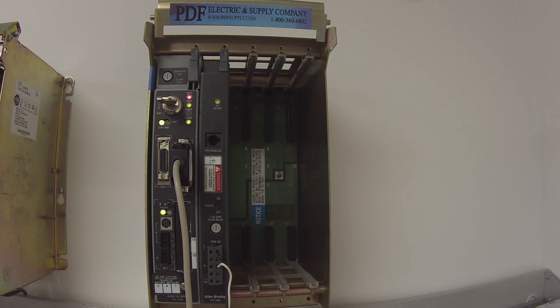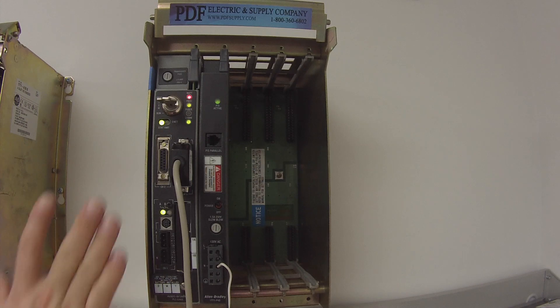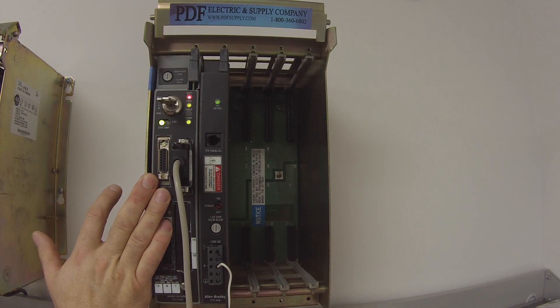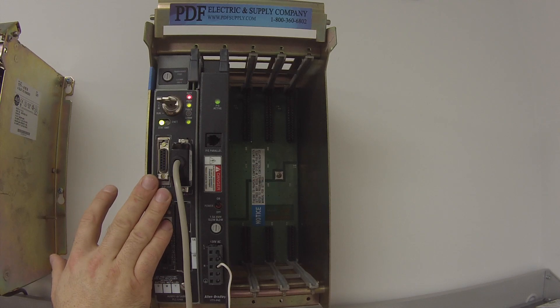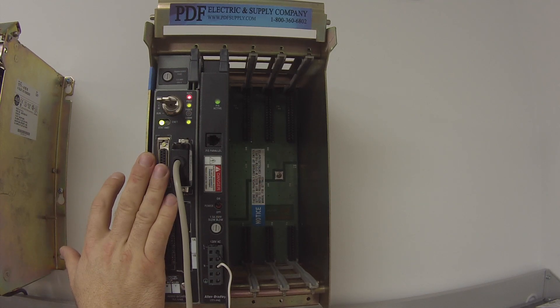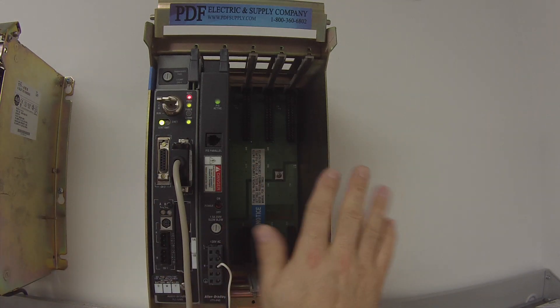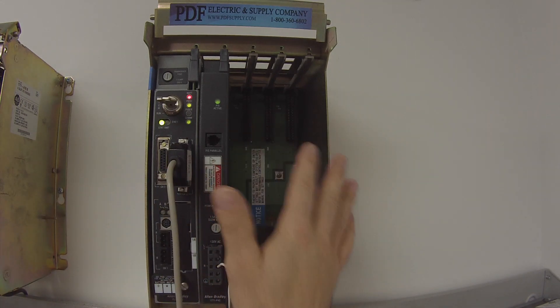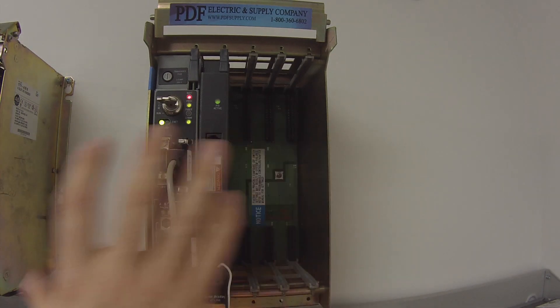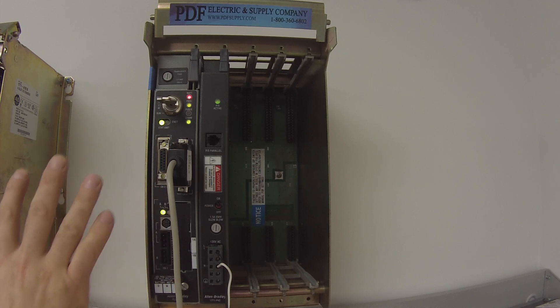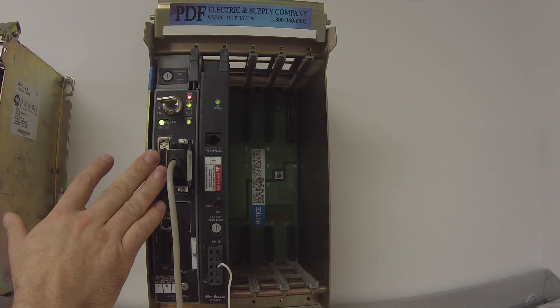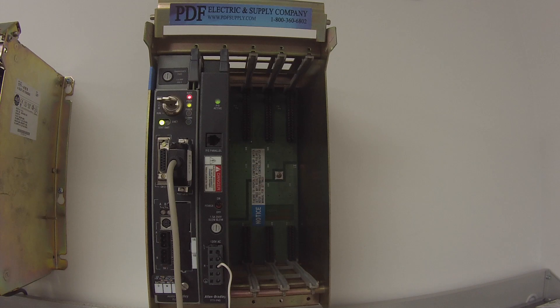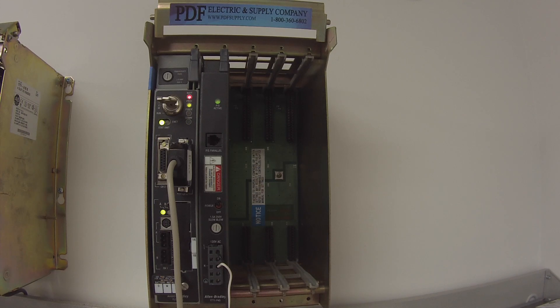So that's generally what we do to test these processors if we feel it's troubled. Make sure that it can go into run mode. Another thing that you would want to do is to leave this processor in run mode for a day, a couple days, maybe over a weekend, two or three days. And what you want to do is try to see if you can make it kick itself out of run mode. Perhaps put I.O. modules to the right to fill up the rack. You can cover the bottom with plastic, the top with plastic so that heat has difficulty escaping and it puts the processor under a little bit more strain just to test its durability. So if it fails, then you could always go to the processor status and find out what the errors are and see if it's something that you're able to figure out yourself. If it doesn't fail and it stays in run mode, we feel that it's a good working processor.